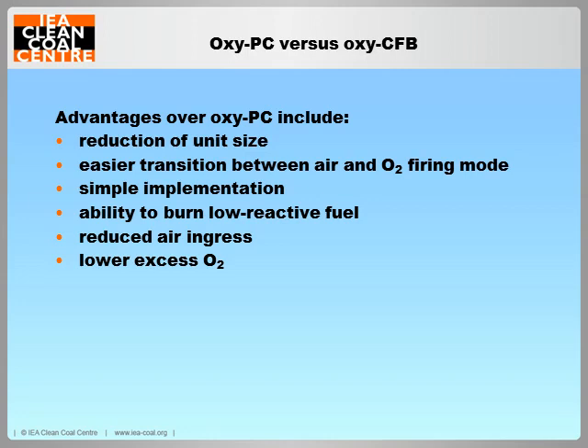An Oxy-CFB system has all the advantages of the CFBC technology and has some additional advantages over Oxy-PC. The combustion temperature in the Oxy-CFB boiler can be controlled by the cooled circulating solids, so the flue gas recirculation rate is minimal. Reduction in flue gas recycling leads to reduced size of the boiler island and some of the power consumption, potentially allowing more compact and less expensive Oxy-CFB boiler.